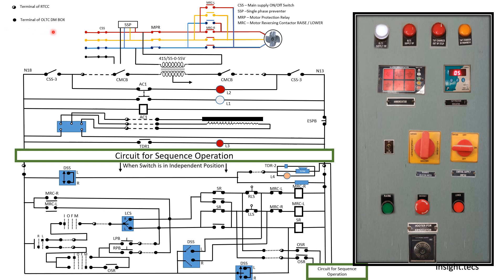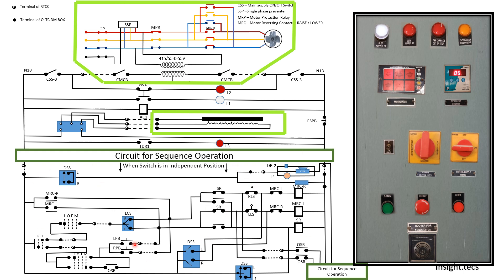In the circuit diagram, this kind of terminal indicates terminals for the RTCC panel, and a complete dot indicates terminals of the OLTC DM box. If you differentiate in this circuit, the two highlighted parts are the circuit of the OLTC DM box, and the remaining part is the circuit inside the RTCC panel. In the lower part, the maximum circuit is of the RTCC panel except the highlighted DM box portion.